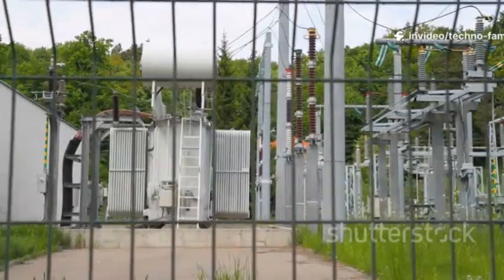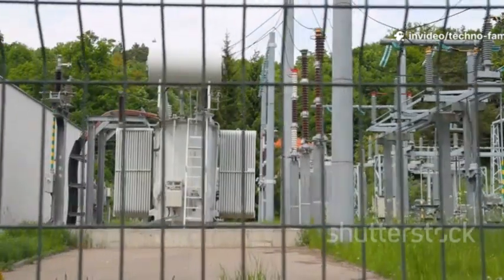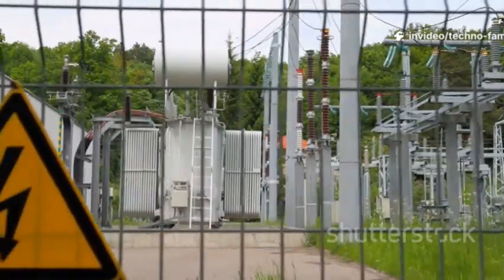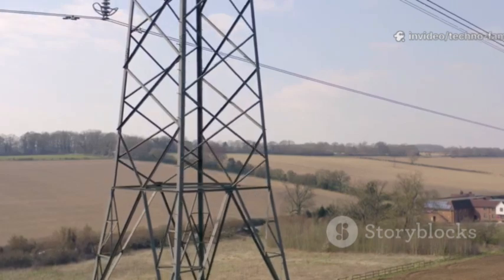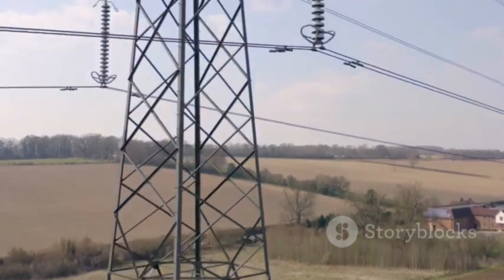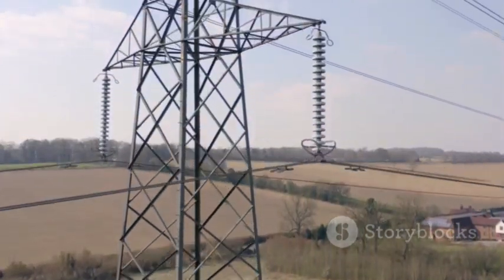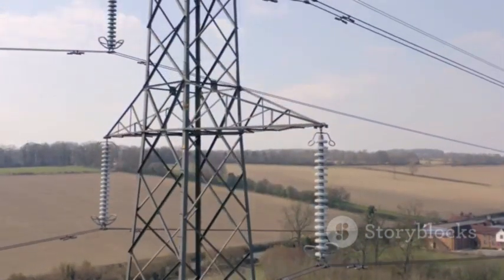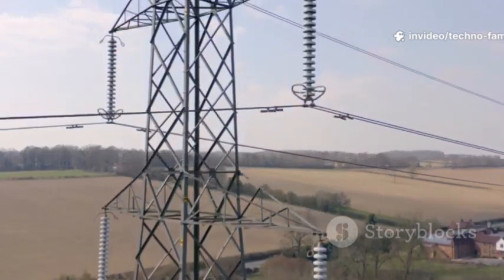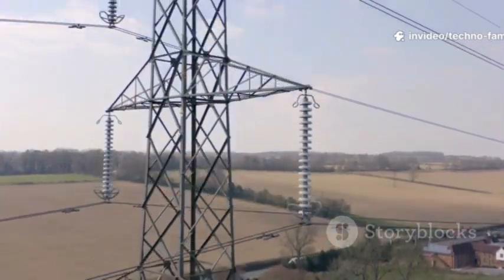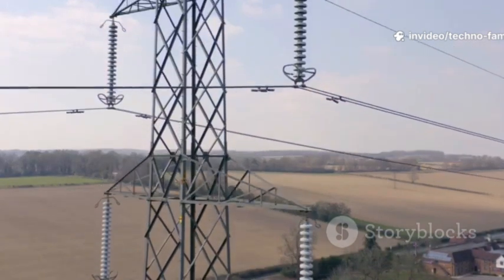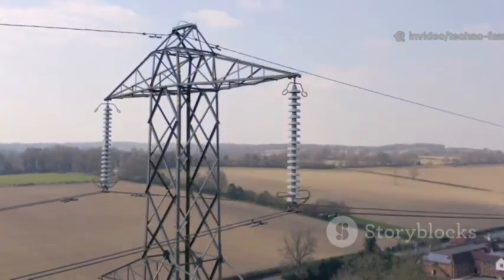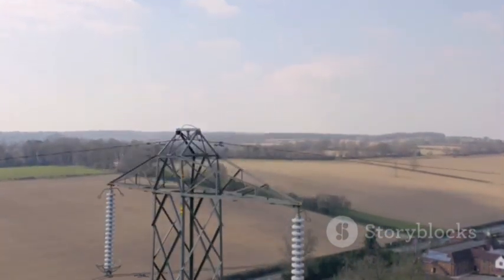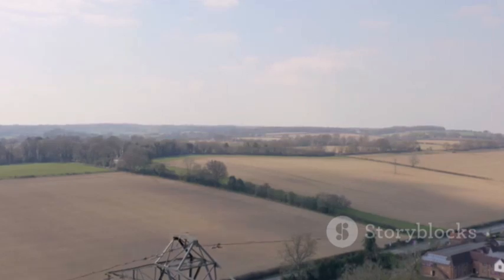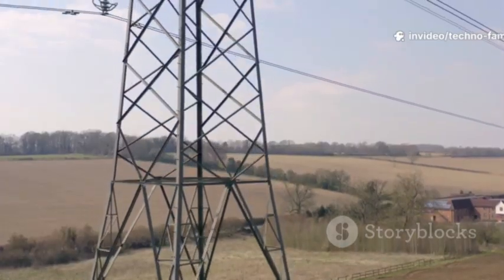AC, alternating current, has been standard for over a century for transmission due to ease of transforming voltages. HVDC, high voltage direct current: for very long distances, approximately 600 km for overhead lines or about 50-80 km for submarine cables, HVDC can be more efficient. Less reactive losses, no skin effect, can interconnect unsynchronized grids. But conversion stations, AC to DC and DC to AC, add complexity and cost.